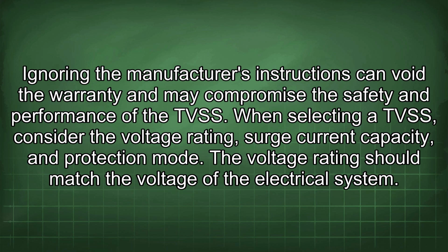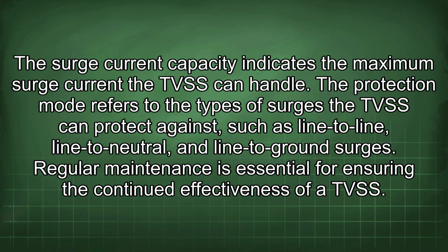When selecting a TVSS, consider the voltage rating, surge current capacity, and protection mode. The voltage rating should match the voltage of the electrical system. The surge current capacity indicates the maximum surge current the TVSS can handle.